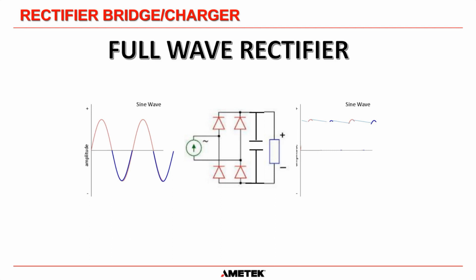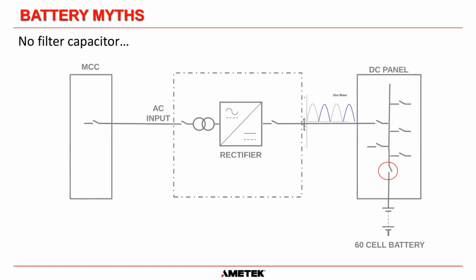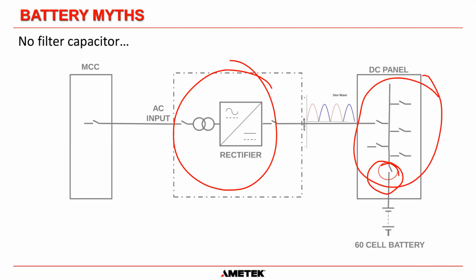This one here shows you what it should look like when you add a capacitor to the circuit. You can see this is pretty much flat DC. There's just a little bit of ripple on there. So if you had an unfiltered charger and you opened the battery breaker here, these load circuits, whether they are trip and close supplies or auxiliary circuits connected to the DC, are going to be exposed to this. And that is probably around 170 volt peak if it's a 120 volt input system, and that does go down to 0 volts.